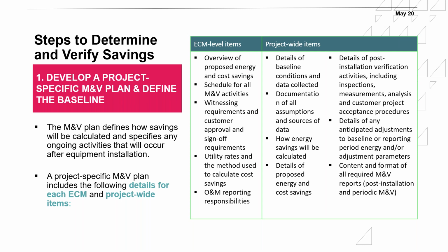You need to define what the ECM is, what it is going to do. Schedule all M&V activities related to the ECM, what needs to be captured. Witnessing requirements: you might need to go with the customer and get their sign-off that they've seen it and they're okay with it. Utility rates: what are the utility rates to be used? In some projects, you might have a different rate than what's being used by the utility, for different reasons. Could be that it's a utility pilot project and they are using a higher rate just to decrease the life cycle cost of the project or the simple payback of the project.